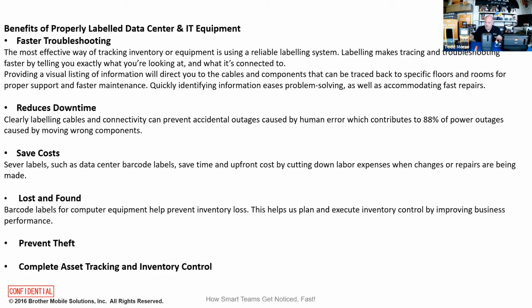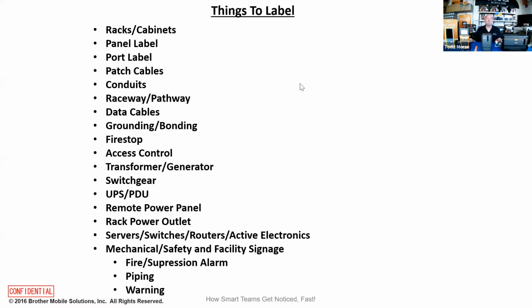Now, you have your asset tracking and inventory control, which can be significant. Here's some of the core components of the types of labels you put inside data centers: racks and cabinets, panel labels, port labels, patch cables, conduits, raceway, pathway, data cables, grounding, bonding, fire stop, access control, transformers, generators, switch gear, UPS, PDU, remote power panel, rack power outlets, service switches, routers, active electronics, passive electronics, and mechanical safety and facility signage, which includes fire, suppression alarm, piping, and warning.